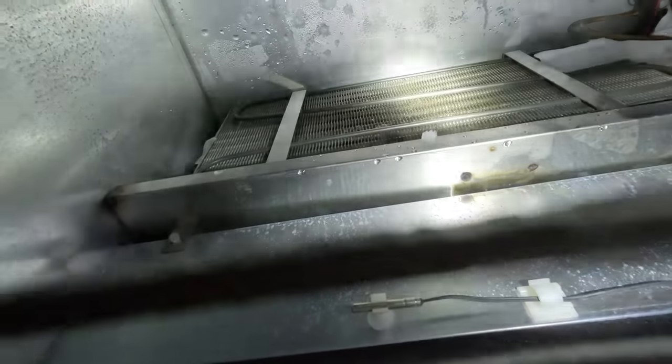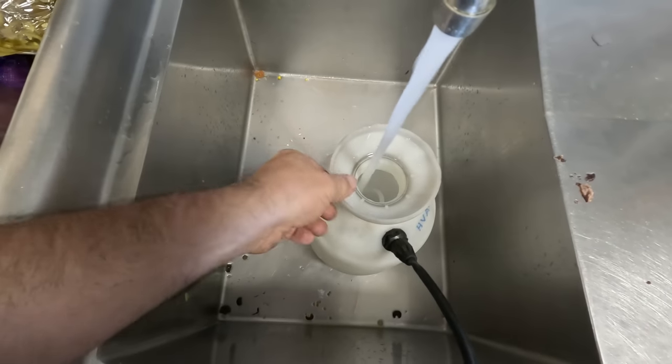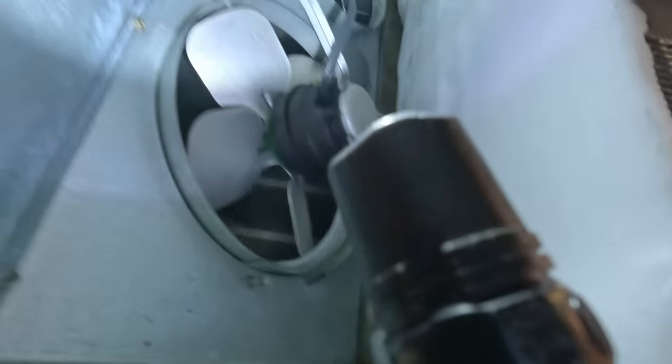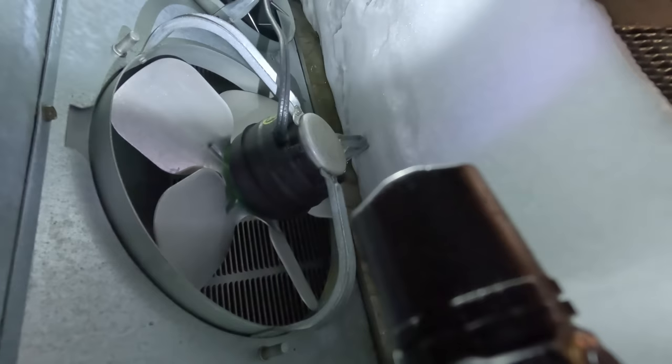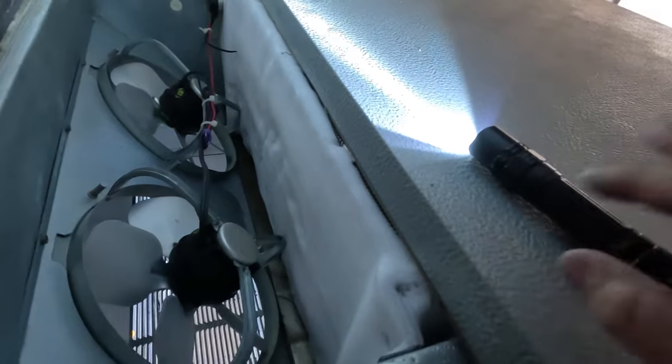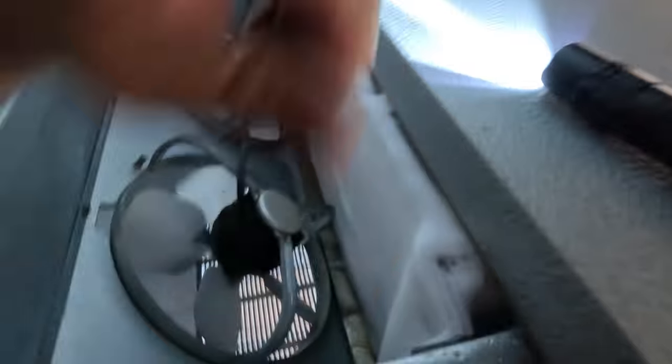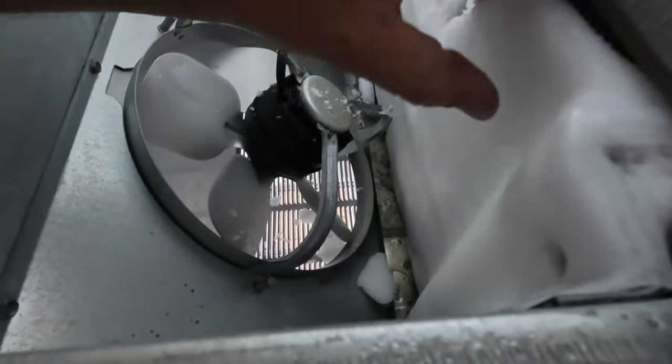Alright, so I've got a pan catching here, a pan catching there. All that stuff fell, most of it, all fell off the coil. Actually, all it fell off except for the one edge corner. Probably got a little bit at the back too that might fall. Wiped up this floor. So I got to get some rags and wipe that all up because you don't want that to freeze in here. That worked out better than normal just because the extra water, like I said, would have filled up that pan and it would have went potentially all over the place. Well, it hasn't kicked on yet. That's still running. That's still burning up. See if we can scrape some of that crap off. Trap that heat over there on that side. See if we can peel this off. Yep. Good. We can peel this off. There's your defrost termination limit switch over there. Fans feel good. That's good. This little gizmo here is made for scraping gaskets and stuff like that.